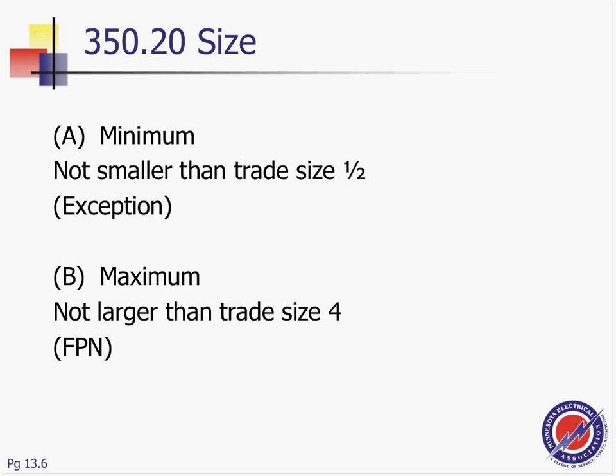Bring it on. You have from 1/2 inch all the way to 4 inches. The exception, guys, is 3/8 of an inch. Same rule, 3/8 of an inch. With the flexible metallic conduit, we can use it for motor connection. We can use it for fixtures. When you get the 3/8 of an inch, they refer you to 348.20(A), and it says no problem. Go tie it to the leads of a motor. 6 feet to tie to equipment or fixture, no problem. Manufactured wiring, no problem. In hoistways for elevators, problem, and in listed assembly for wired luminaires, no problem. So that 3/8 is a very limited application.